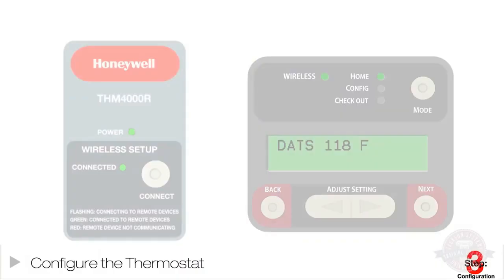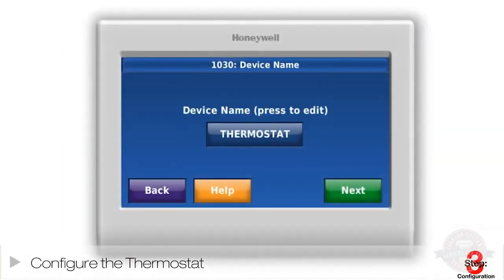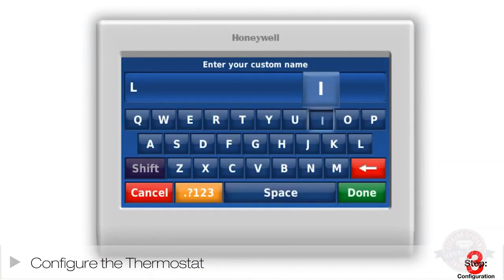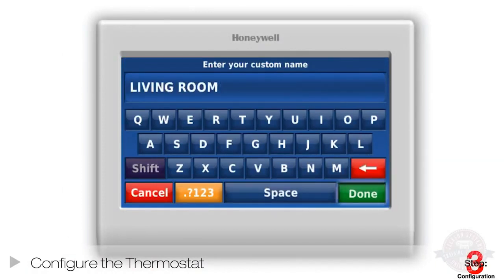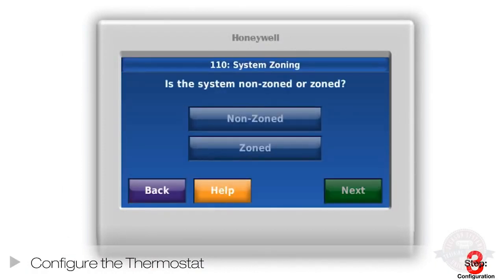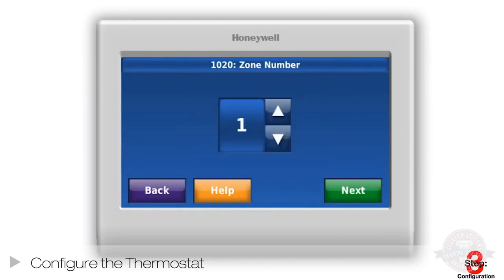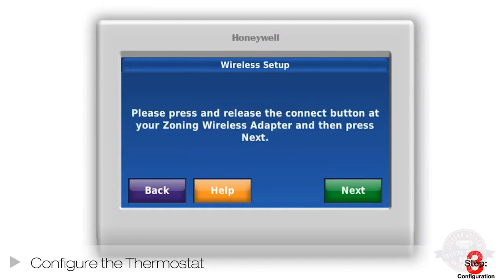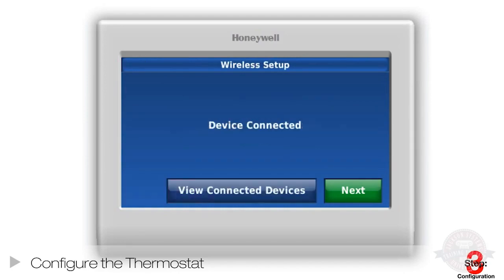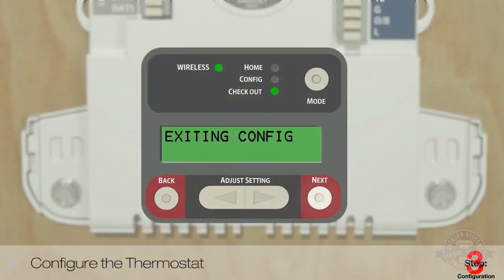At the thermostat, select the proper zone and name the thermostat. Hit Connect to enroll the thermostat to the Zone panel. Repeat these steps for all remaining RedLink thermostats in the home and any RedLink accessories, including an outdoor sensor, internet gateway, or portable comfort control. Go to the Zone panel and exit RedLink Setup by hitting the Mode button. Your devices are now enrolled and thermostat configuration is then complete.